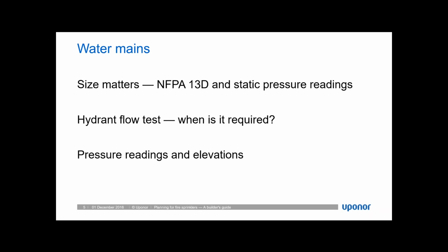However, for 13D sprinkler systems, the flow required is often very, very small compared to the larger sprinkler systems seen for 13R or 13 systems. Sometimes as little as 26 or even 20 gallons per minute is all that is required to supply a residential sprinkler system. Therefore, hydrant flow tests may not be required for every sprinkler system installation in residential development. I do want to caution, however, that if the local water authority or the fire department, or whomever the authority having jurisdiction is, requires that flow test, it will still need to be conducted and used in the design of the system.